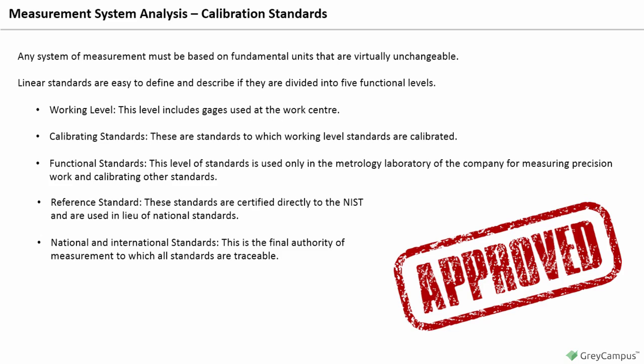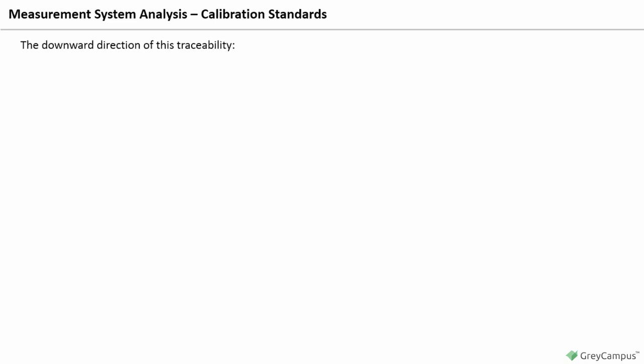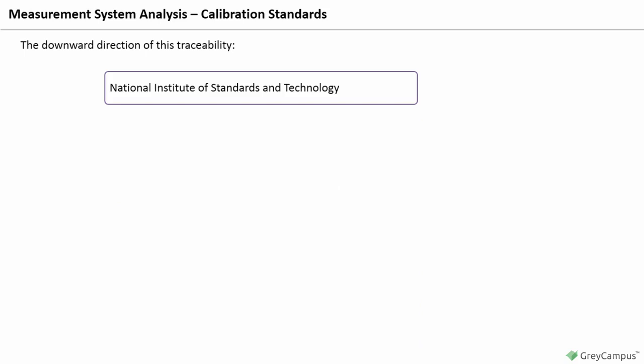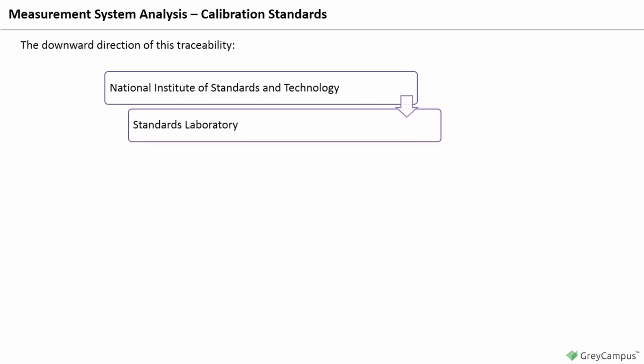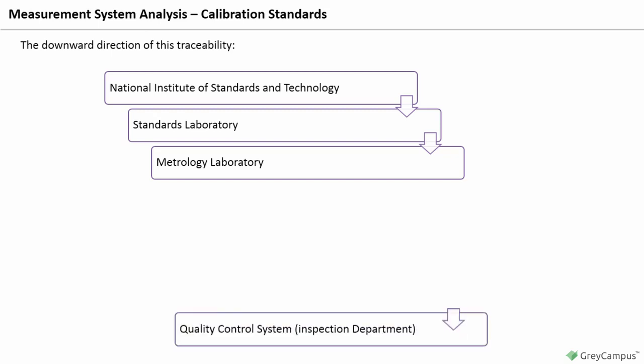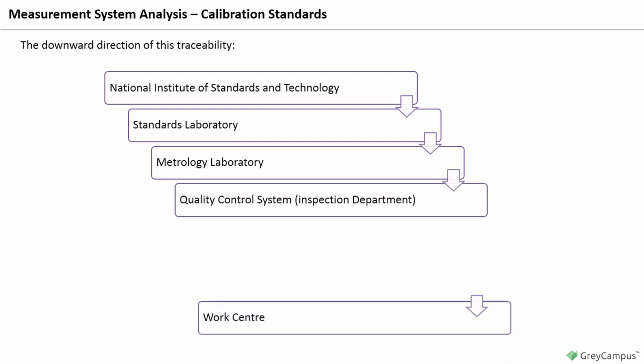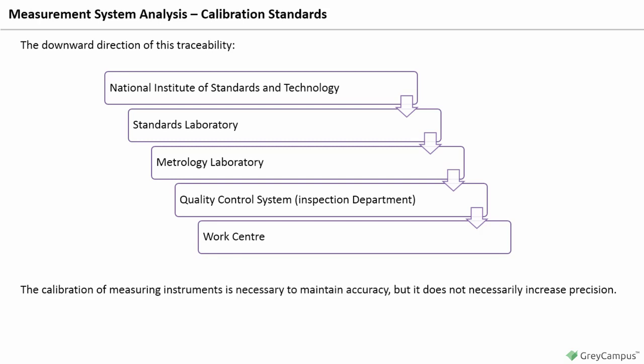Since the continuous use of national standards is neither feasible nor possible, other standards are developed for various levels of functional utilization. National standards are taken as the central authority for measurement accuracy, and all levels of working standards are traceable to this grand standard. The downward direction of this traceability is shown as follows. National Institute of Standards and Technology, Standards Laboratory, Metrology Laboratory, Quality Control System or Inspection Department, Work Center. The calibration of measuring instruments is necessary to maintain accuracy, but does not necessarily increase precision. Precision most generally stays constant over the working range of the instrument.